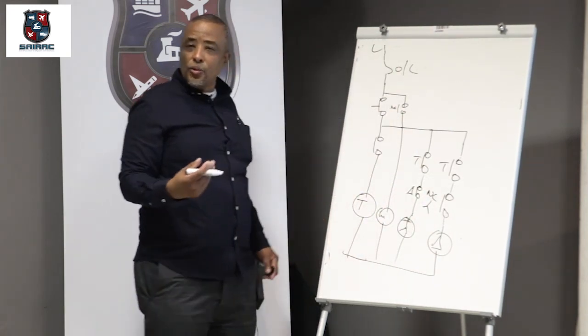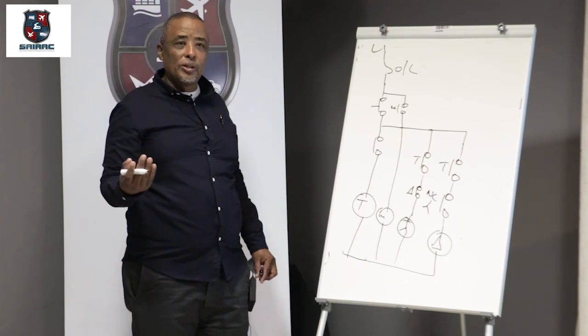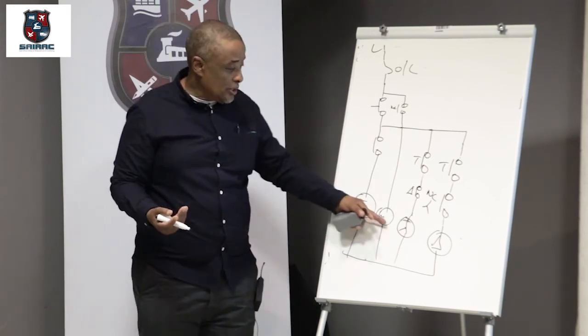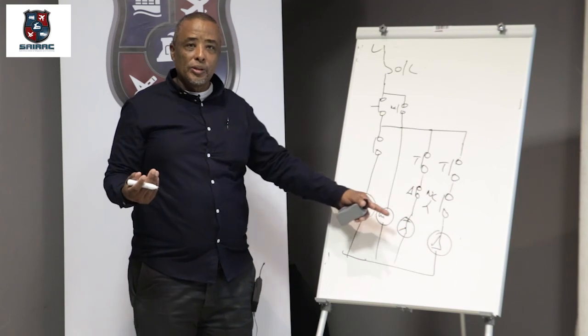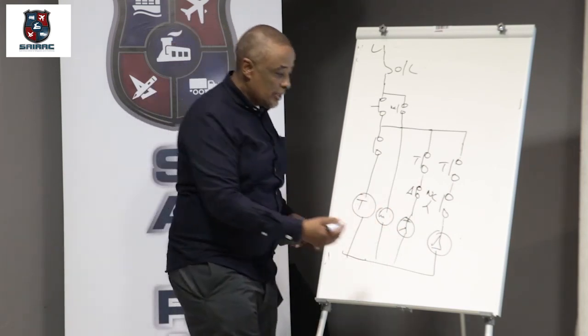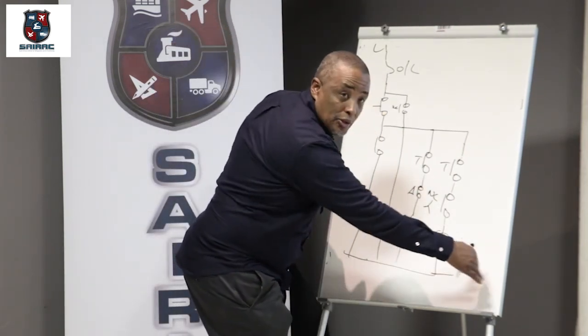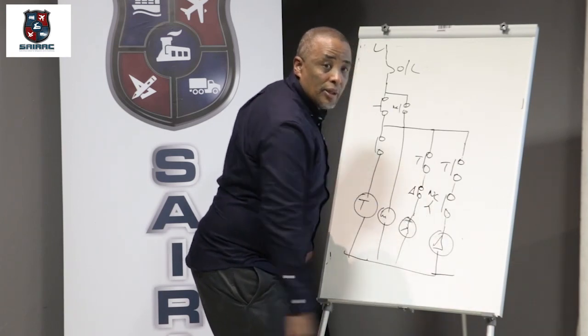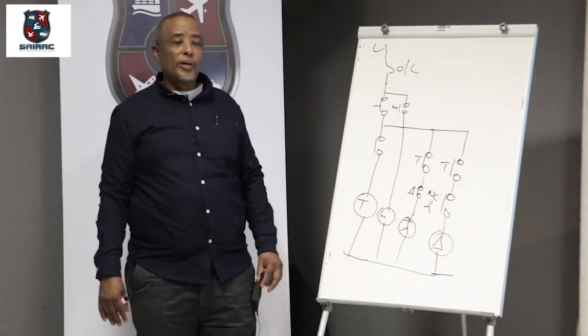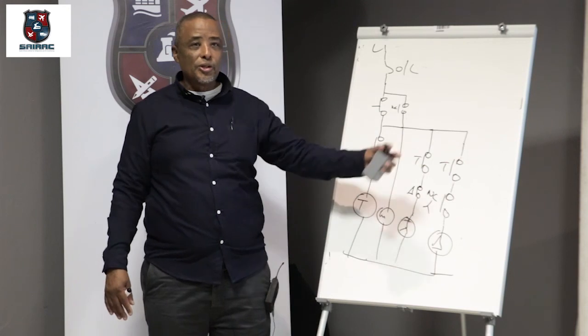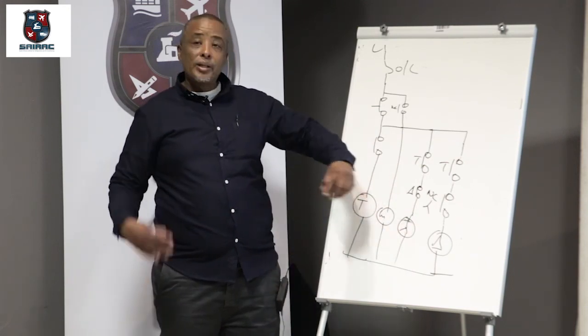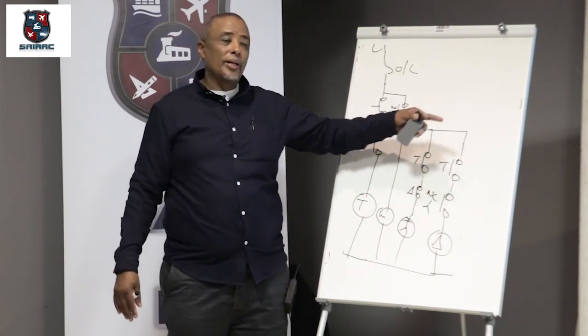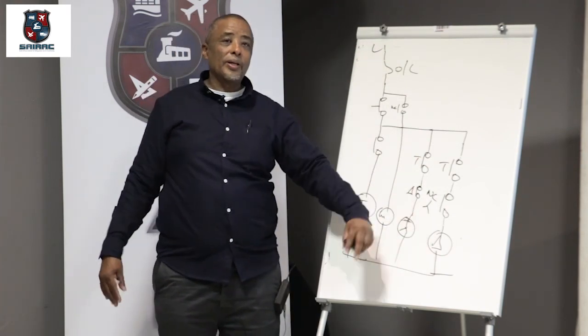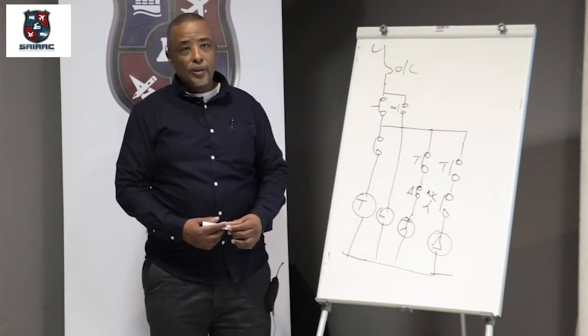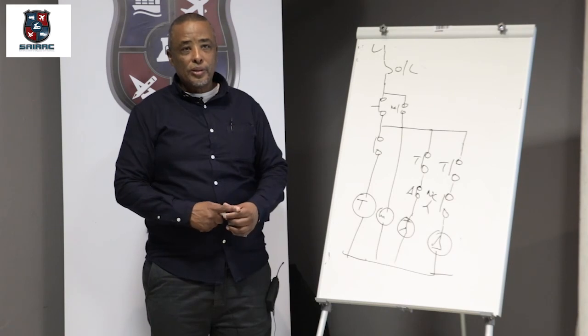The control circuit is normally 12 volts, 24 volts. Okay. And obviously these coils here will be 24 volts. So on this side here as well, you could even put whatever controls you want to add here. Thermocouples, whatever sensors you want, proximity switches, any other sensors, any other protection you want to add to it, you can just add it either there or you can have it there in series. Whatever your other controls are.